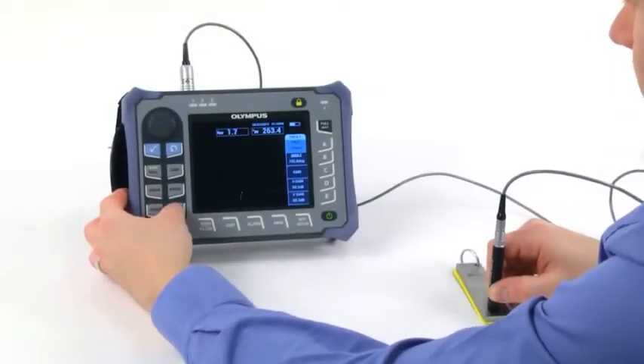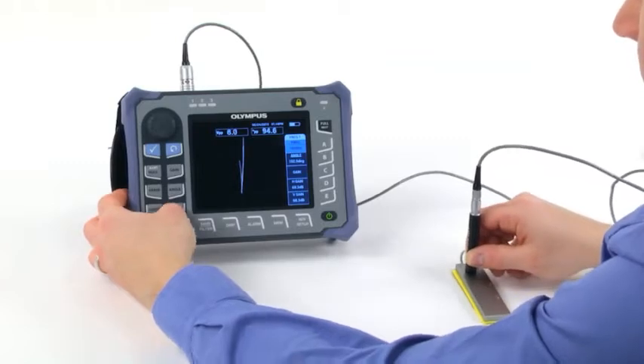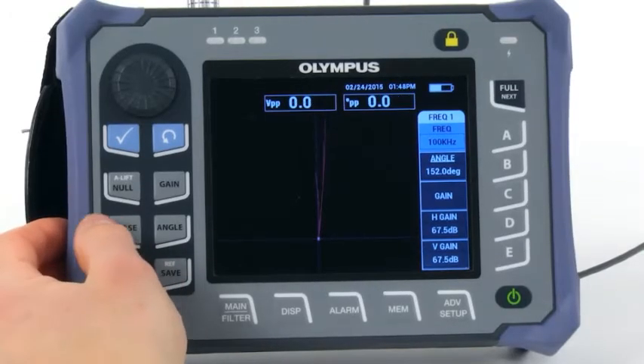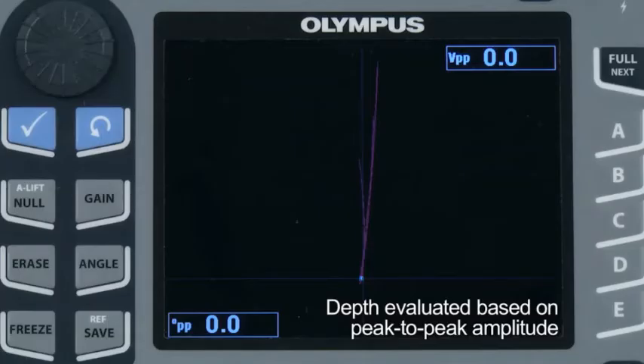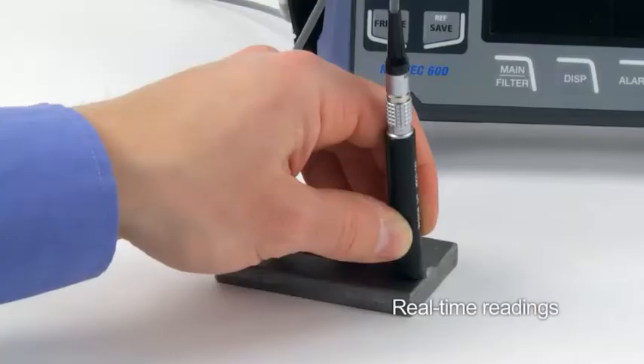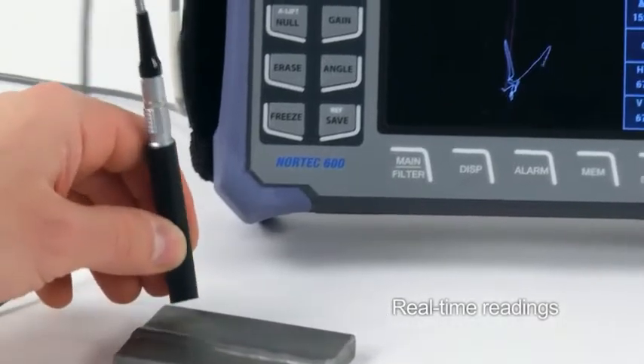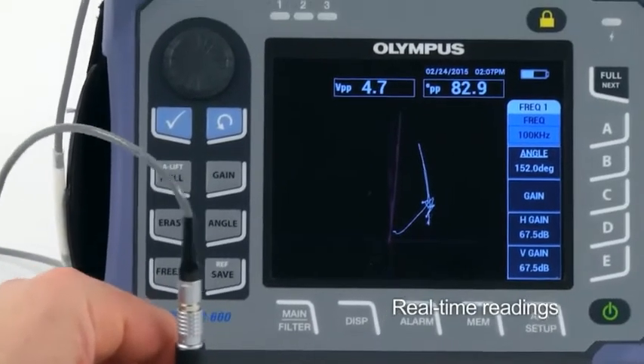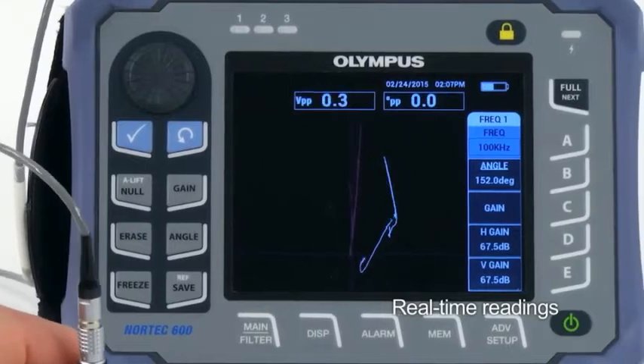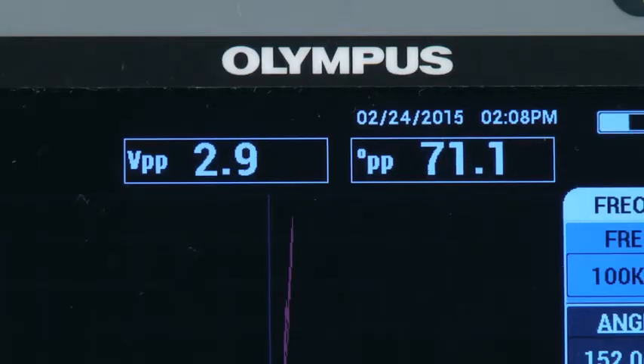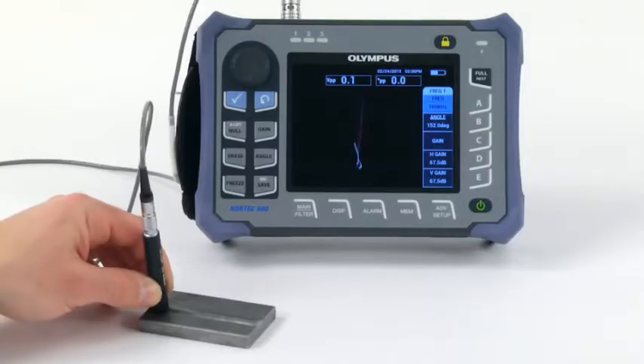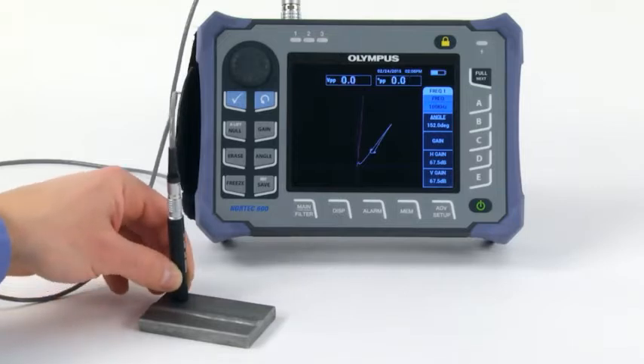The Nortec 600 weld inspection solution features unique tools that facilitate the evaluation of an indication's depth and length. The depth of a surface breaking indication can be evaluated based on the peak-to-peak amplitude in the impedance plane; deeper indications produce larger amplitudes. The new real-time readings provide instantaneous amplitude and phase values that can be used for comparison with calibration defects. This peak-to-peak measurement is a very reliable and consistent way to determine an indication's depth, because variations in the operating point have no effect on it.